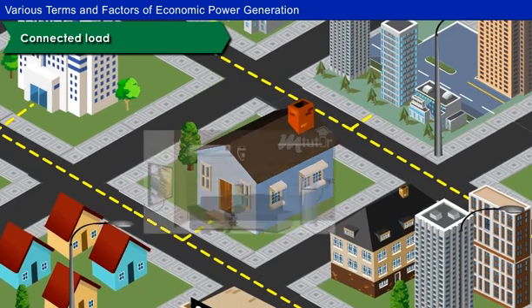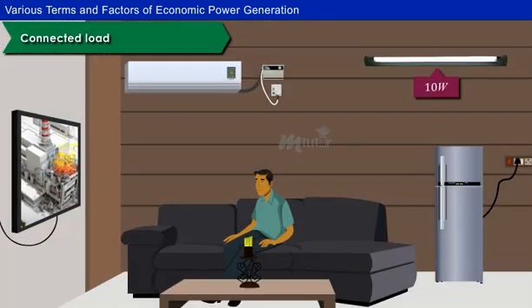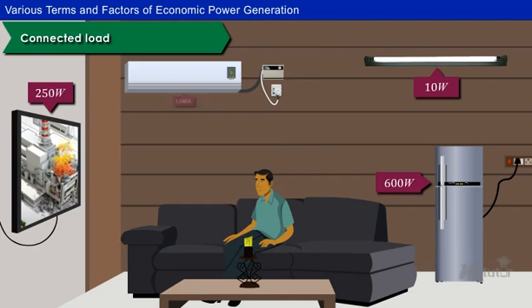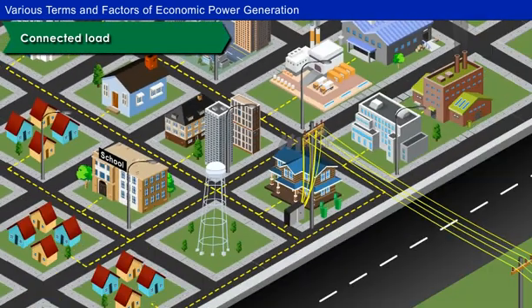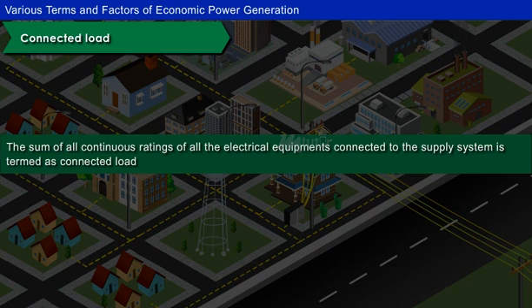The sum of all the electrical equipment in the consumer's premises that are connected to supply and are in operating state is collectively called the Connected Load of the Consumer. For example, if a residential consumer uses a 10W fluorescent lamp, 250W flat screen TV, 600W refrigerator, and 1200W air conditioner, then the connected load of the consumer is equal to 10 plus 250 plus 600 plus 1200W, which is equal to 2060W. Likewise, the sum of all continuous ratings of all the electrical equipment connected to the supply system is termed as Connected Load.